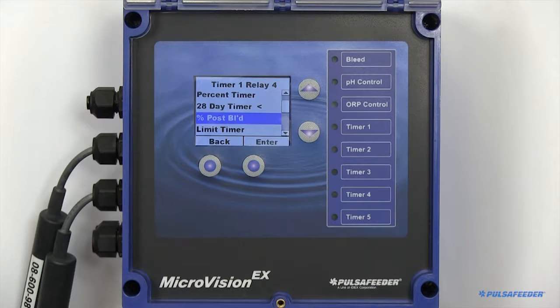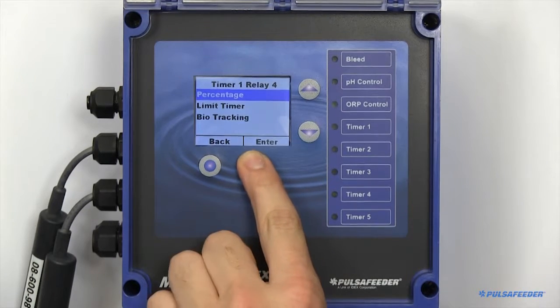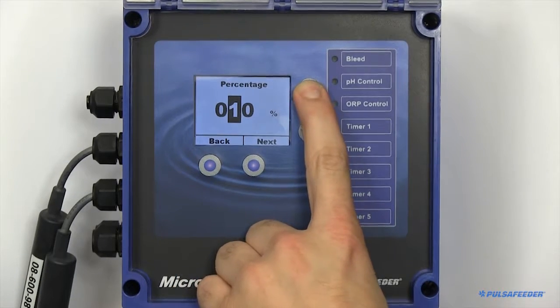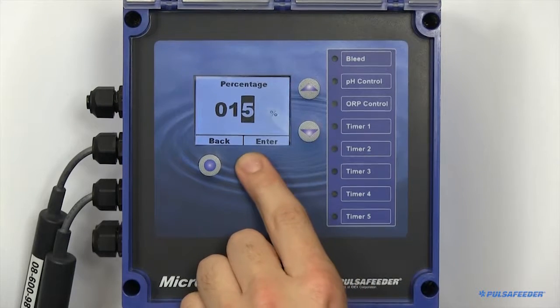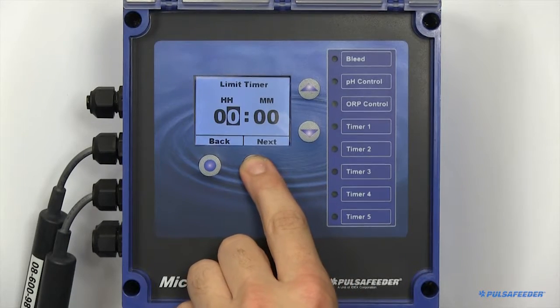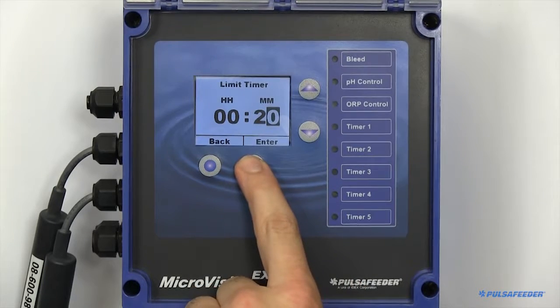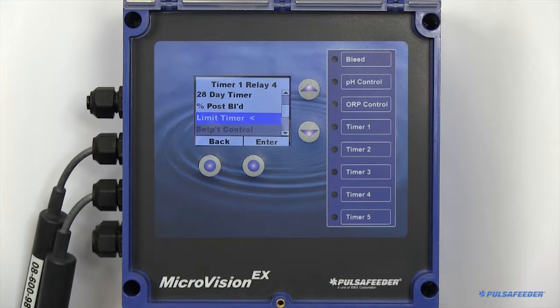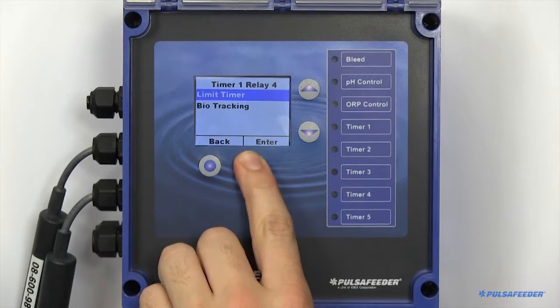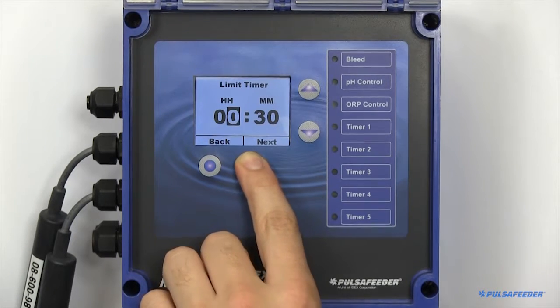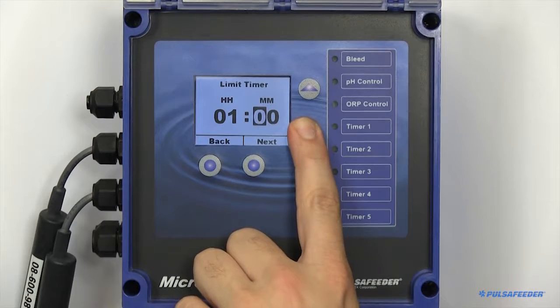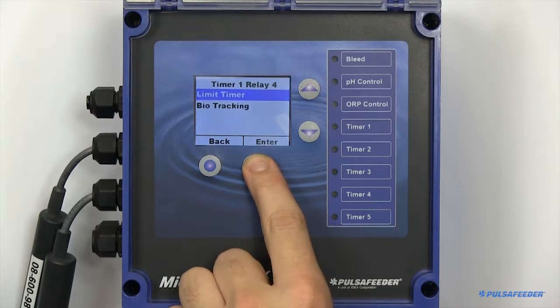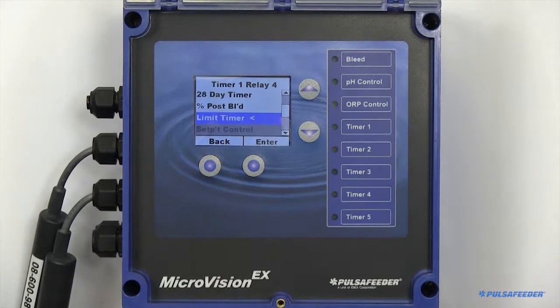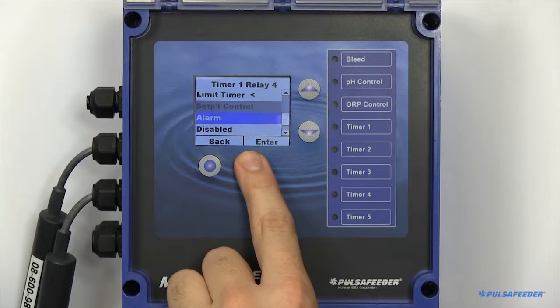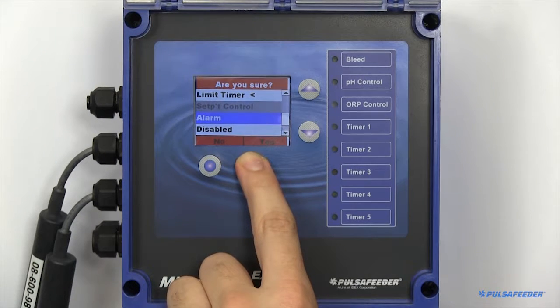Percent post-bleed keeps track of the time the bleed relay is turned on. When that bleed shuts off, it will then bleed for the specified percentage. The timer also includes a limit timer to prevent overfeeding. A limit timer, also known as a bleed and feed timer, will mirror your bleed relay. This timer also has its own independent limit timer. You can also configure any of these timers to be alarms. They will turn on when any alarm on the system is present.